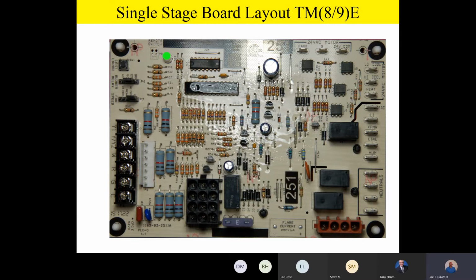So without further ado, if everyone will please reference the left-hand side of the PowerPoint screen. Let's go over the low voltage terminals to start with and review those real quick, just to make sure everybody's singing off the same page. So looking over here on the left-hand side, Y1, that's your first stage cooling call, and that's pretty standard in the industry. I think that's pretty universal in the industry. So Y1 would be your first stage cooling call if you have a two-stage product outside. Y2 would be your second stage cooling call from the thermostat.